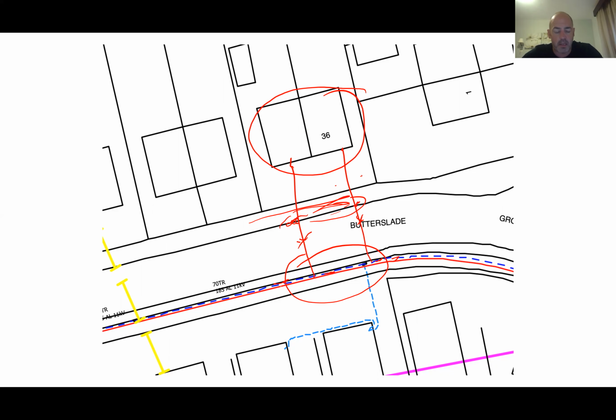And on that subject, when we look at cable strike investigations, there was one that I saw recently where the team hit a cable to a house, and it was just like this. It wasn't shown on the plan, and the outcome of the investigation was that the cause of that cable strike was because it wasn't on the plan. Is that really the cause, though? We should know, shouldn't we, that buildings have a power supply, and if that's the LV main and that's the building, it's got to get there somehow. So another little example there for you.